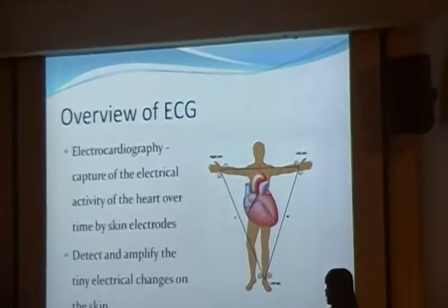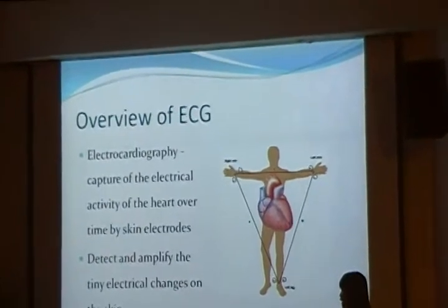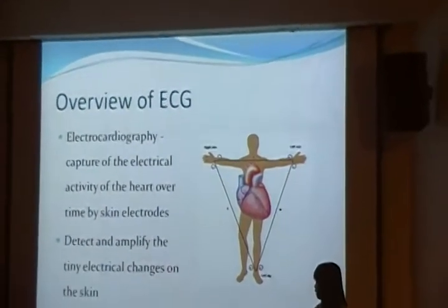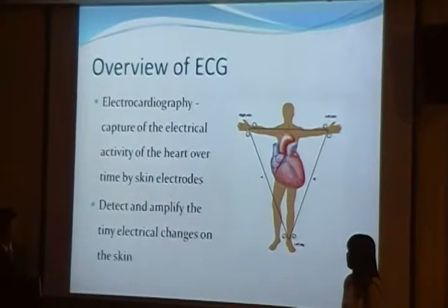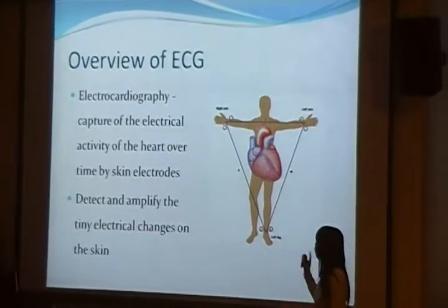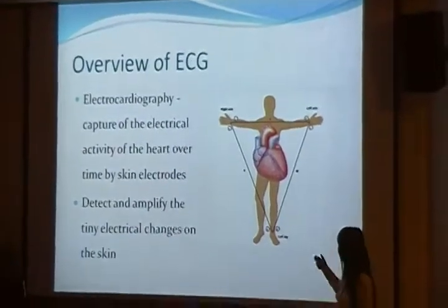It also detects and amplifies the tiny electrical signals on the skin. We use 3 electrodes, one on the right hand, one on the left hand, and one on the leg.